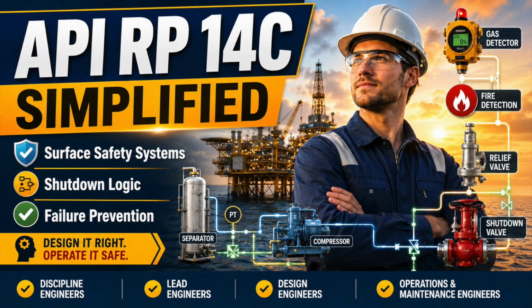At every design review, ask direct questions. What can overpressure this equipment? What high-pressure source can reach this low-pressure section? What does this shutdown valve actually isolate? What backflow inventory does this check valve control? Where does the liquid go after high level? What downstream equipment is threatened by low level? What release is this gas detector expected to see? What fire location can this detector actually detect?